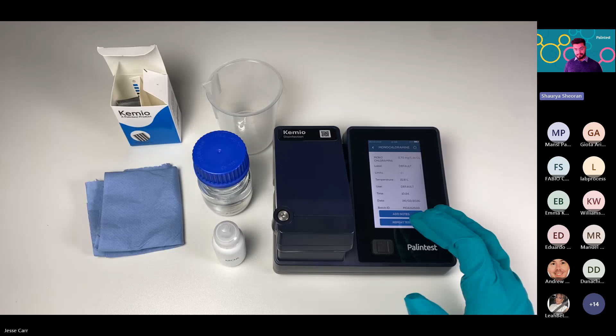As you can see, we got our monochloramine reading. And if you want to get some of the details of that reading, just click on details and you can see the temperature of the water sample, the time the test was performed, the date, and the batch ID for that sensor information. And if you wanted to do another test, let's say you're running multiple tests back to back, you just hit repeat test and it guides you through the setup for the repeat test.